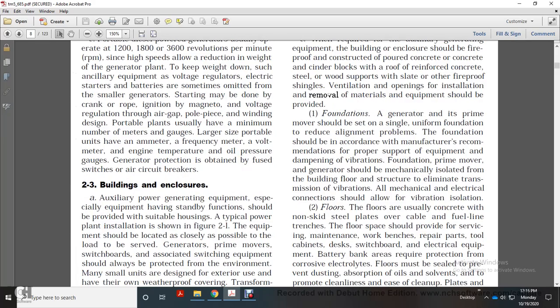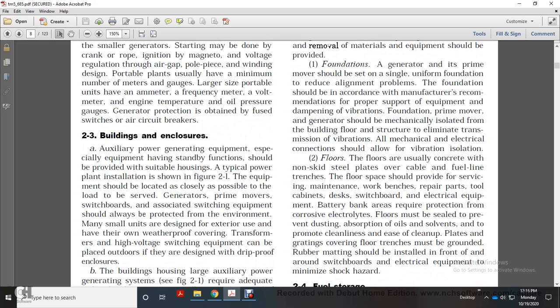The generator and prime mover are mounted on a single uniform foundation to reduce alignment problems. The foundation should accord with manufacturer recommendations for proper support and vibration dampening. The prime mover and generator should be mechanically isolated from the building floor to eliminate transmission of vibration. Mechanical and electrical connections should allow for vibration isolation. Floors are usually concrete with non-skid steel plate, and cable and fuel line trenches are provided. Floor space should allow for maintenance workbench, repair parts, tool kits, switchboards, and electrical equipment. Floors must be sealed to prevent absorption of oil and solvents. Covering of floor trenches must be grounded.